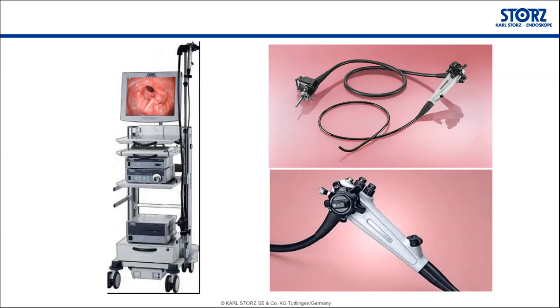During the day you can hang it like this. Right now you can see it is on the hanger, but if you are finishing a day, I would request that there should be a special almirah where the endoscope can be hung, so that if any water droplet is there inside, it will come out, so that the endoscope is completely dry. And at the end of the day, kindly perform the leakage test.